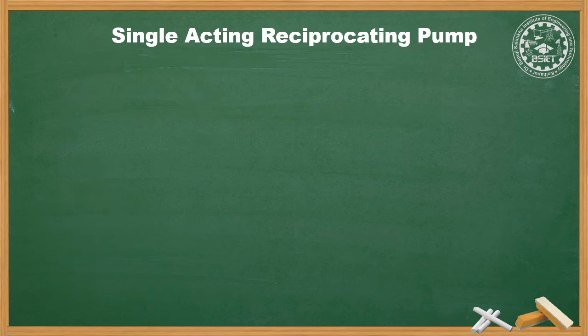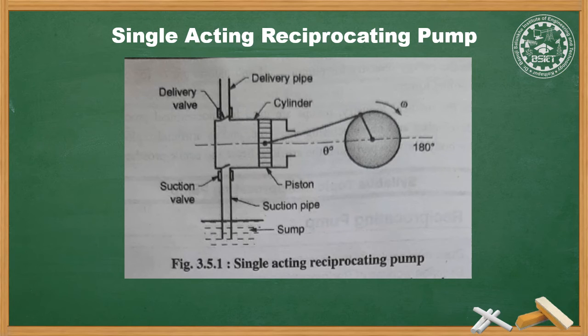Starting with the first type: the reciprocating pump, also known as the plunger pump. Plunger pumps are reciprocating positive displacement pumps with a to-and-fro motion — backward and forward in the horizontal plane, or up and down in the vertical position. This consists of a cylinder with a reciprocating plunger or piston closely fitted in the cylinder, along with suction and discharge valves mounted in the cylinder head, a piston-crank mechanism, and suction and delivery pipes. The valves are spring-loaded and operate according to the pressure developed during the to-and-fro motion of the piston.